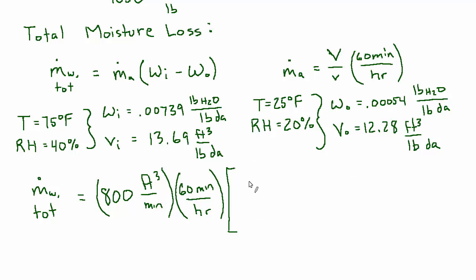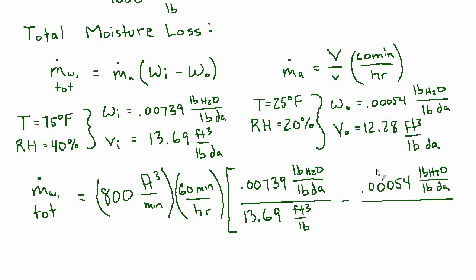So we'll do the inside first because that's the high humidity: 0.00739 over 13.69 cubic feet per pound. And by the way, you're welcome to work in grains, I chose to work in pounds here. Sometimes it's easier to use grains because you'll have a bigger number, probably an integer number. For the outside term we have a humidity ratio of 0.00054 and a specific volume of 12.28.